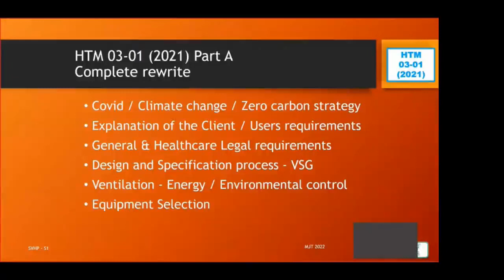There's also information about installation requirements, simple things. As I've said, I've been an authorised engineer, and I do acceptance in hospitals. People installing dampers for balancing ventilation systems, without fail, put the handle to adjust the damper at the top. When you put the ceiling up in the room, you can't get at the damper handle to commission it. There's no reason the handle has to be at the top, it can be at the bottom. The air doesn't know where the damper handle is, it makes no difference to the function of the device.